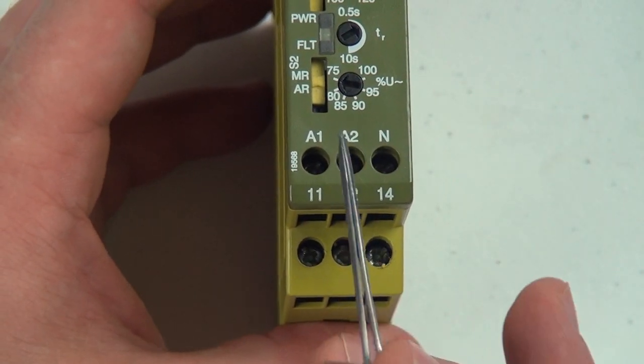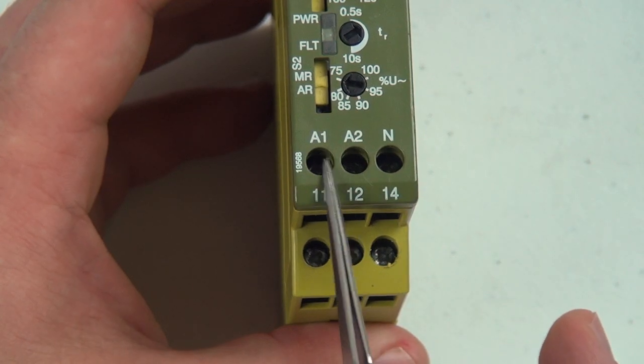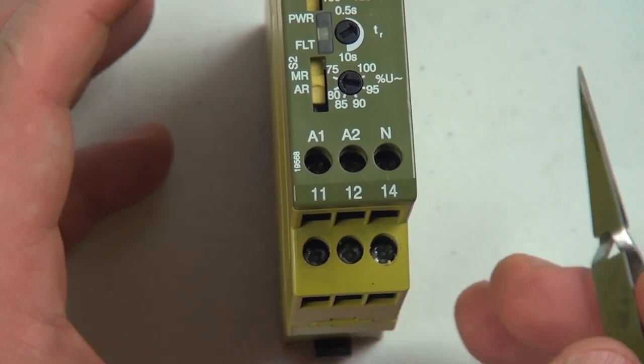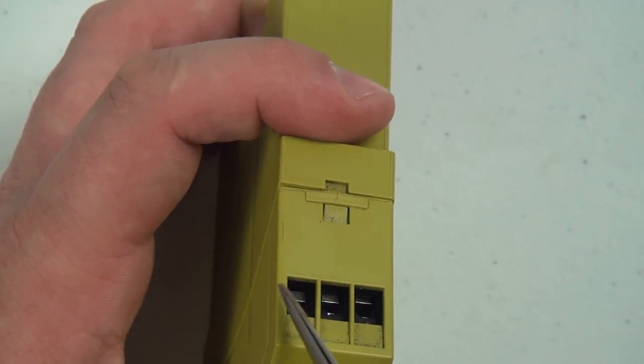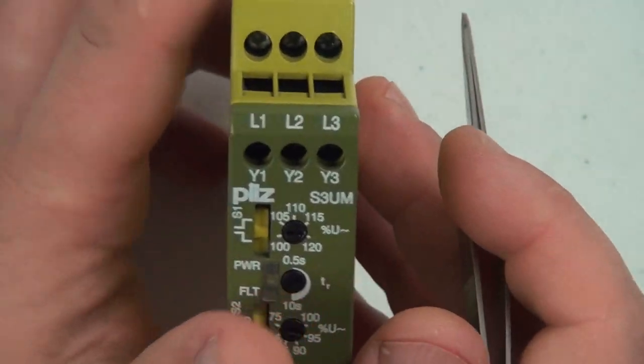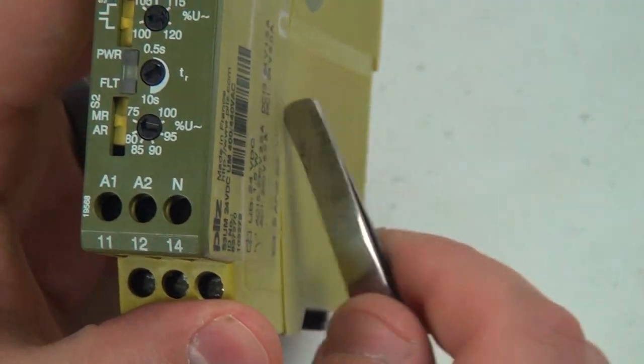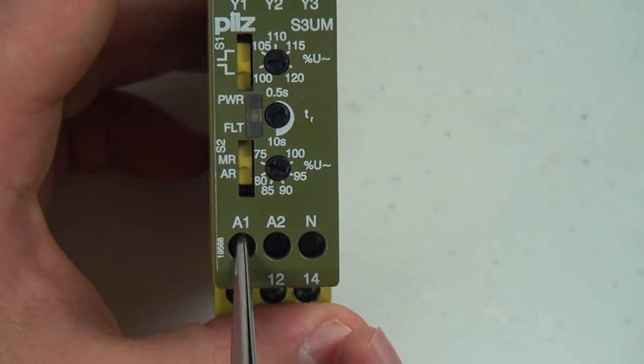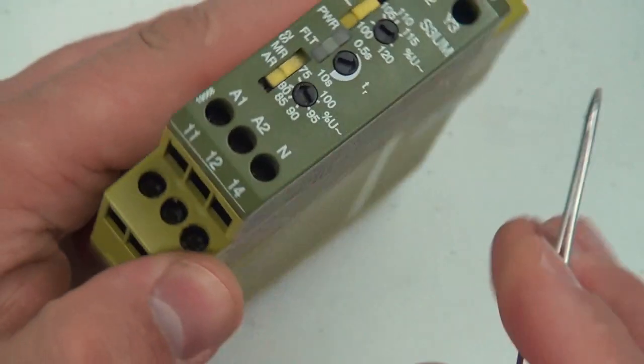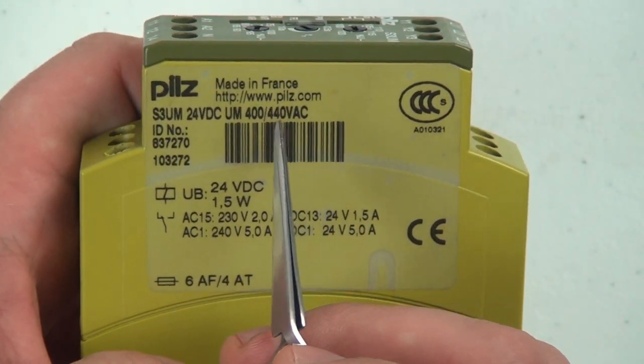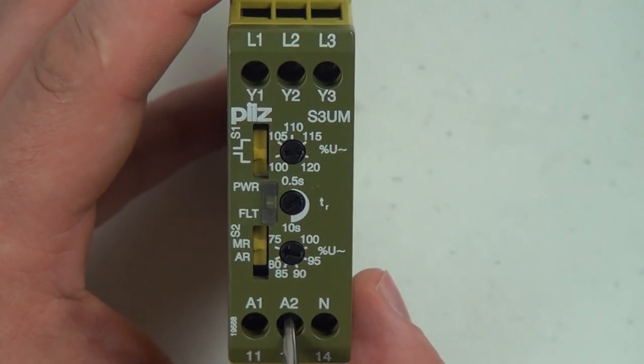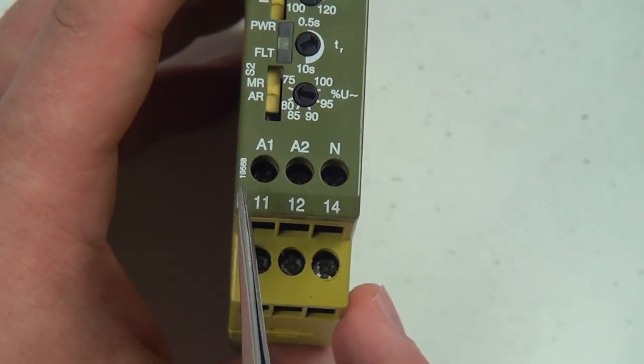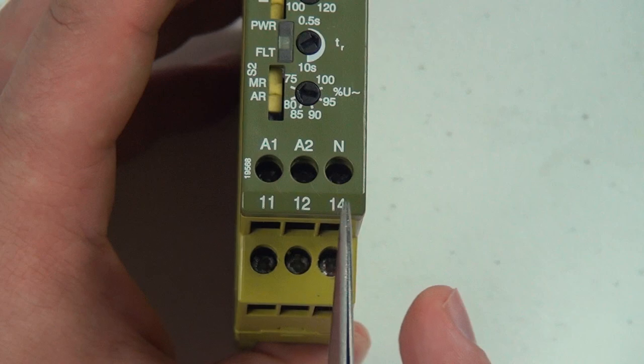So on the bottom here, we already talked about our neutral. A1 and A2 are our power source, whereas you're allowed to put 400 volts on these terminals up here. The actual power for inside of the relay is A1 and A2, and you can put 24 volts DC, like it's stated right here, 24 volts DC into A1 and A2. And finally, we get to 11, 12, and 14.